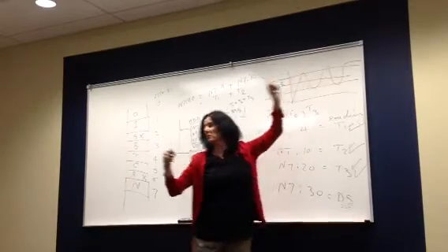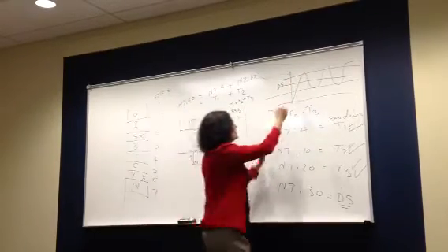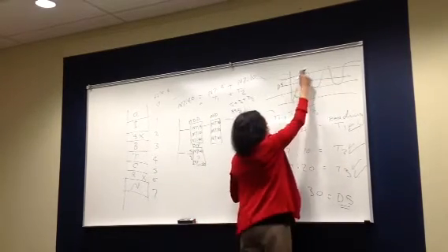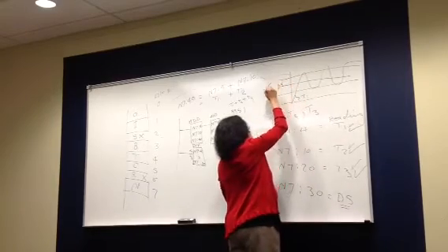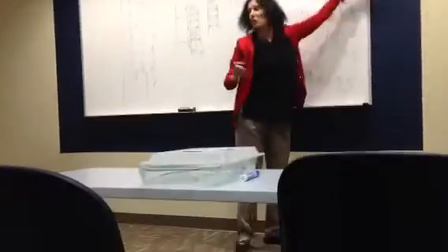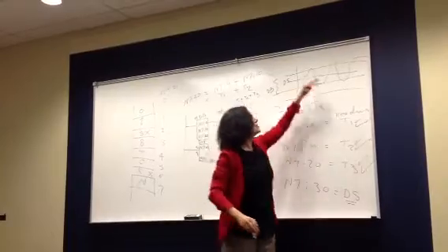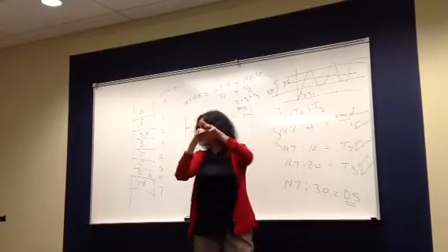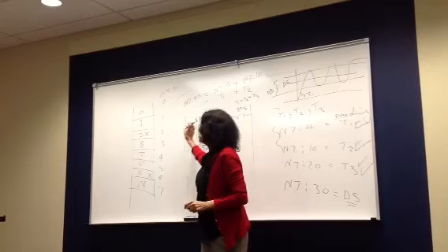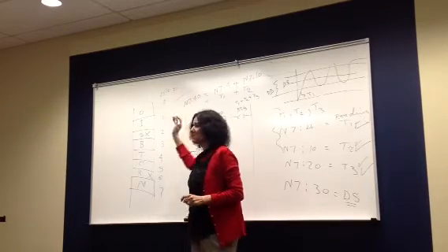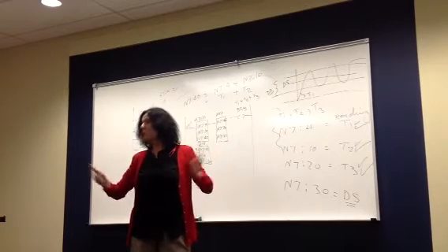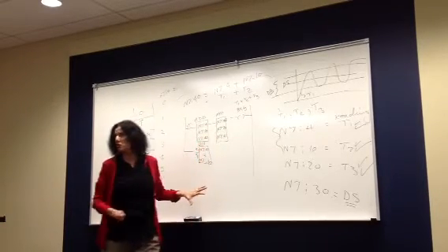I have like a dead band. I take that transmitter one and I repeat it for 2 and 3. That's why I'm saying it's a long story. And I go between a certain dead band here, and if transmitter one, and that's the average, the one in here, N7:30, my average. So if it's above or below, I disconnect it and take the average of the other two. So I put a condition here. But I don't want to do that with you right now. It needs one complete course. But at least you know how to get the average, right?